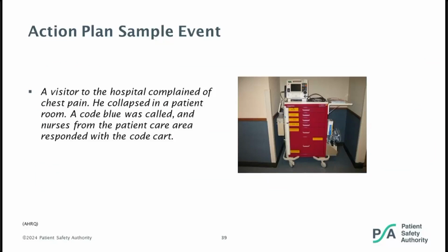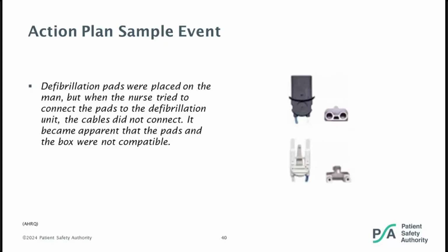Nurses from the patient care area responded with the crash cart. In this case, defibrillation pads were placed on the man, but when the nurse tried to connect the pads to the defibrillation unit, the cables did not connect. And it became apparent that the pads and the box were not compatible.